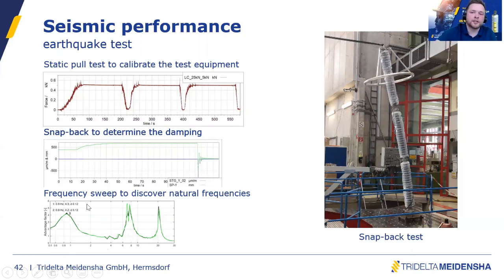And during this, on the top of the surge arrestor, there is a sensor, and you will see that there are different natural frequencies, one fundamental frequency and more harmonic frequencies, where the surge arrestor is swinging with the highest acceleration. And this highest acceleration we take, and then the ground acceleration with this frequency is applied to the surge arrestor by the shaking table.